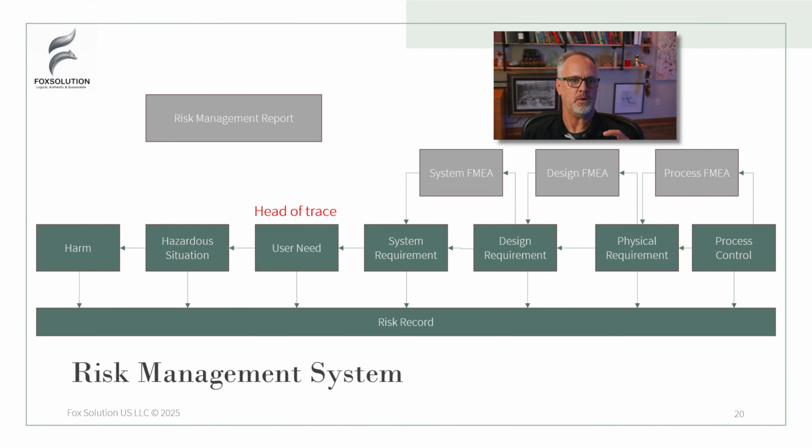This is the report that we want to be able to show to the agency that says we have our processes under control. Now, one of the really cool things about this too is the FMEAs are going to characterize every potential error and the occurrence, our perspective view of what we believe the occurrence of that error is going to be. So what we can also do then is bring in post-market data of any kind related to the harm of users, related to the failure of the system, failure of the design, failure of the process, and we can bring that data back into the system and compare it with what we believe the failure occurrences was prospectively going to be. And that gives us a real nice context to make decisions about how important this problem is.